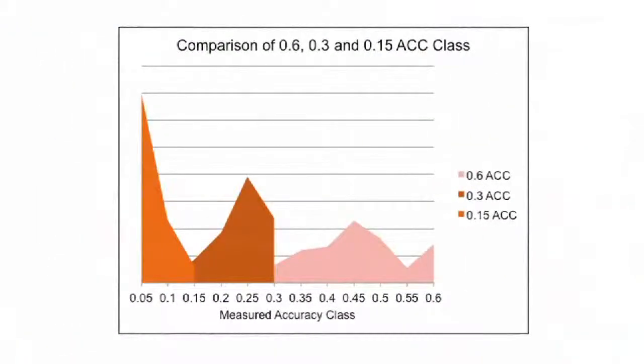So we said, well, let's take a look at some of the data of how our current transformers actually test. We test every current transformer that leaves our factory. So we said, let's take a 10,000 unit sampling of all the data and see where the accuracy truly stands. If we look at what we said before in the 0.3% accuracy class, you can go down to 10%. So we test everything at 10%, has to be at least 0.6% accurate. So we found that the median accuracy of those CTs fell at about 0.45. Okay, so there was quite a bit of inaccuracy as the load went lower.